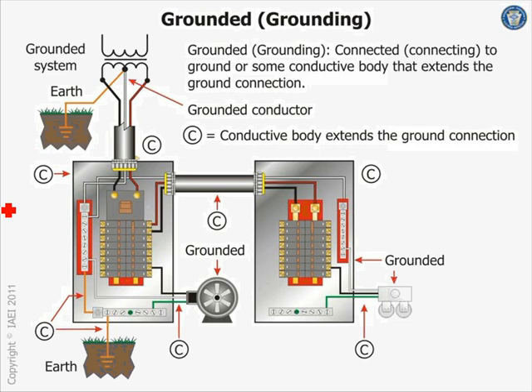A couple of things about grounding and bonding. Like I said, the conduit will act as a ground conductor by extending the ground connection. Look at this, here is my conduit. Everything starts with the ground. Here's my ground right here. That wire extends the ground to here, and then this wire extends the ground to here. So grounding is tying everything to the ground. This conduit bonds the two together and at the same time also extends the ground to this. So you can see everything is referenced to the ground, and my system is referenced to the ground.